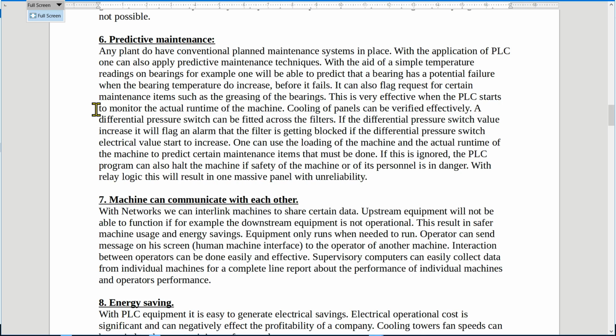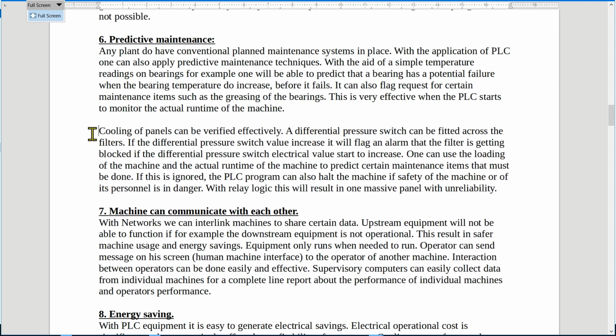For example, I've just added cooling of panels. Now, cooling of panels can be verified effectively. The way we do it is that we use a differential pressure switch which is fitted across the filter. In other words, the one end will measure the pressure inside the panel, and the other point will be outside of the panel, and it will measure the differential pressure between inside and outside. If the filter blocks, the pressure on the inside will actually start to drop, and it will give you an alarm that the filter needs to be replaced.